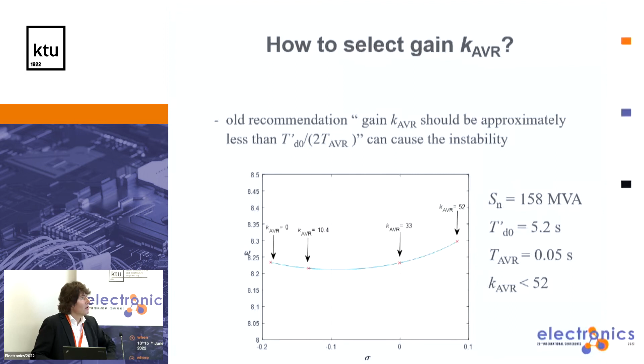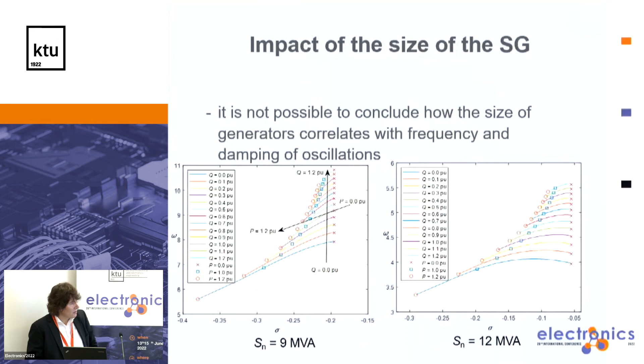So again, I took the same hydro type synchronous generator, but now I equipped it with controls, with a voltage regulator. I will measure the voltage and compare it with the reference stator voltage, and using this automatic voltage regulator and excitation system, I will change the field excitation voltage. So I only add this part to the previous model.